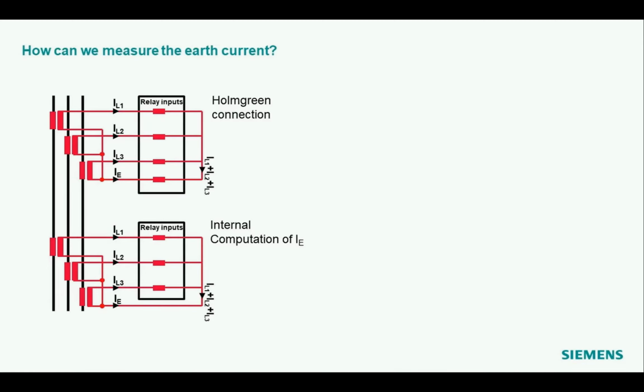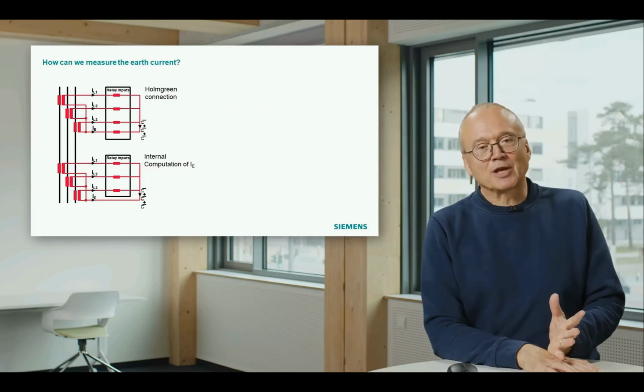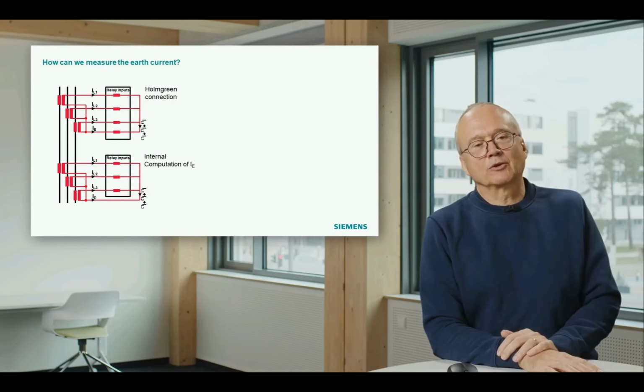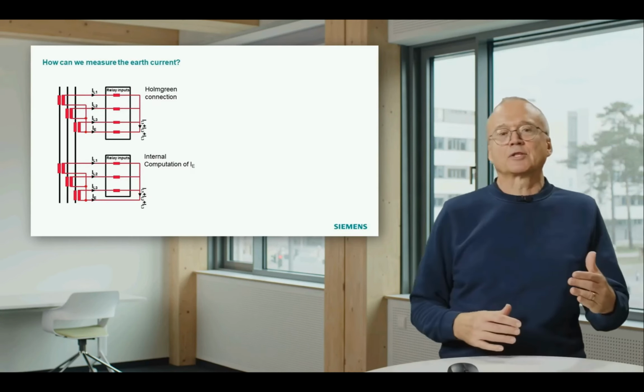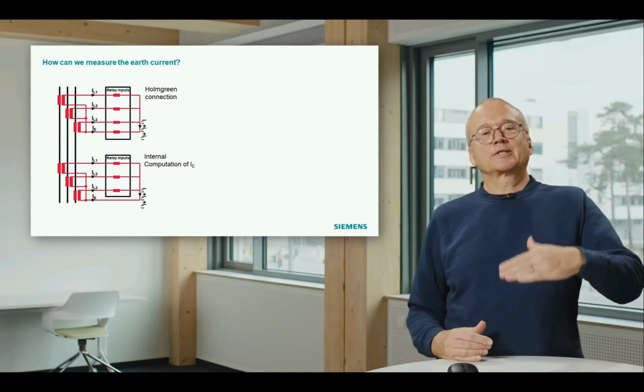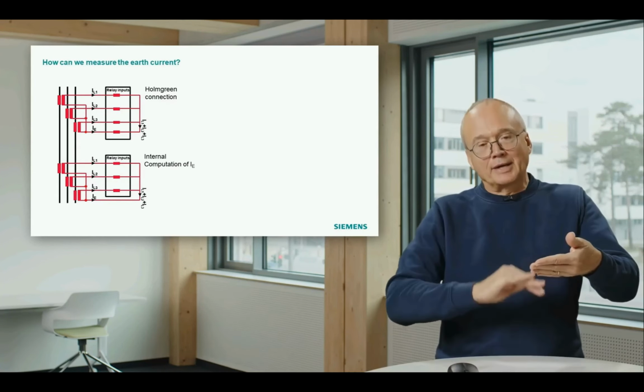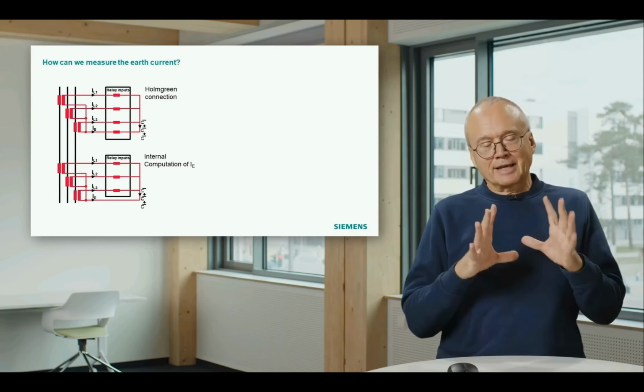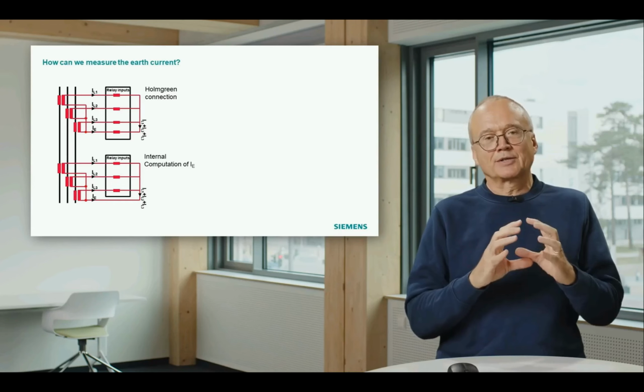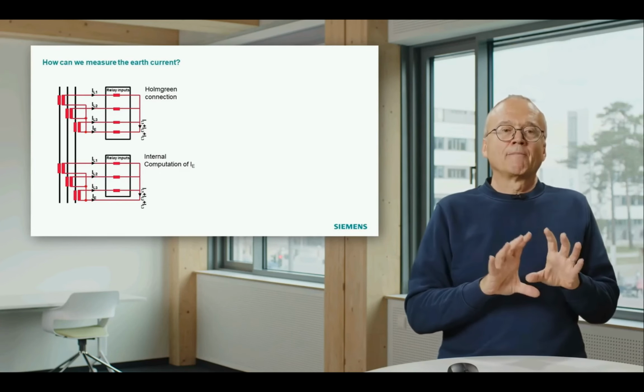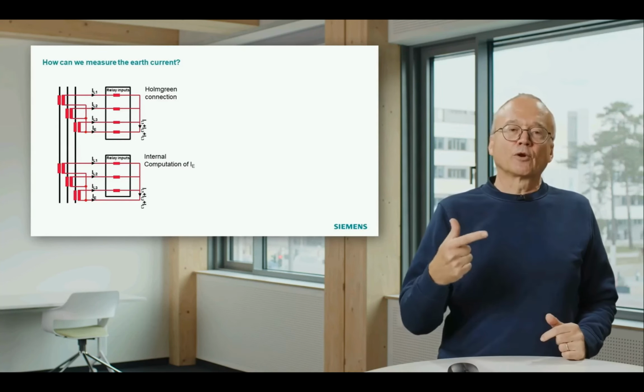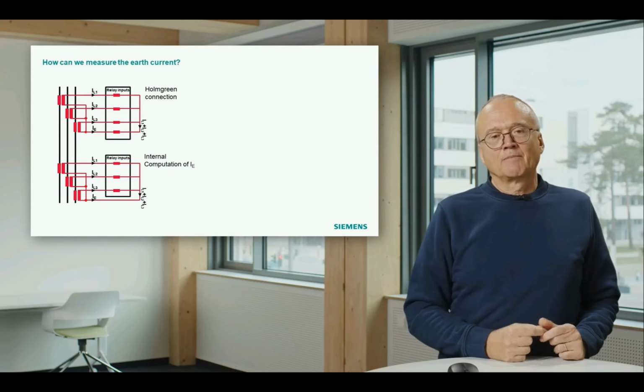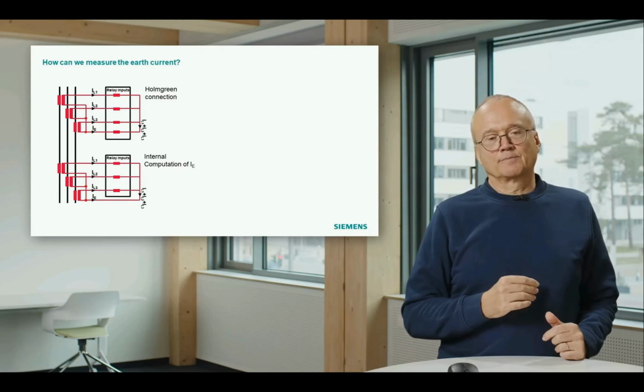You measure through current transformers, and these current transformers may have measurement errors. If all of them have the same measurement error, it's okay. But according to Murphy's law, normally the measurement errors go into the worst direction. You can have the situation that one current transformer has a positive measurement error and another one has a negative measurement error. That means you already get an earth current, even if you have an absolutely symmetrical system, just resulting from the measurement errors of the current transformers. And this has to be taken into account.